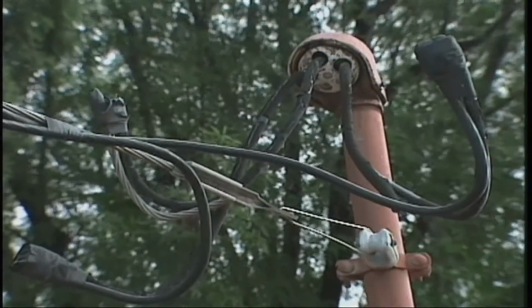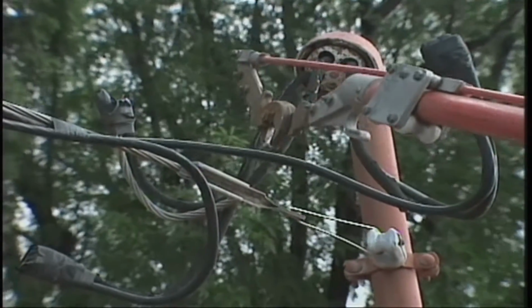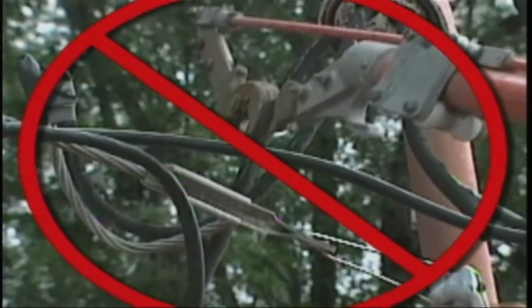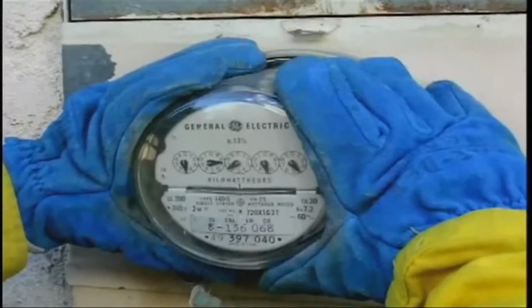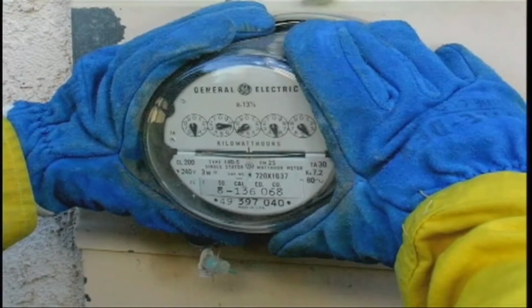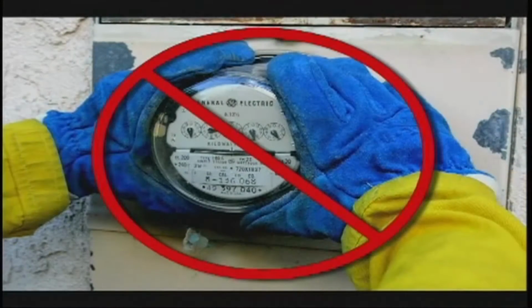We recommend that you never cut any electrical conductor. Cutting wires exposes you to potential electric contact or flashes, which can cause serious, even fatal injuries. If you feel it is necessary to de-energize an electrical conductor immediately, call Edison for assistance. While it may seem obvious, never pull an electric meter to de-energize a structure. Meters are not switches. They could explode.